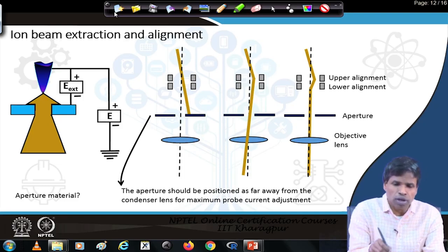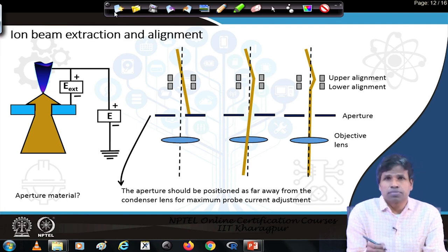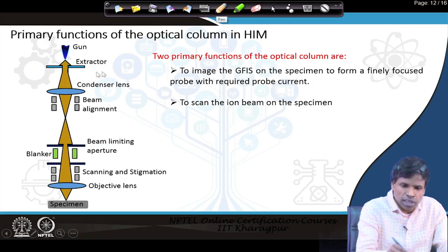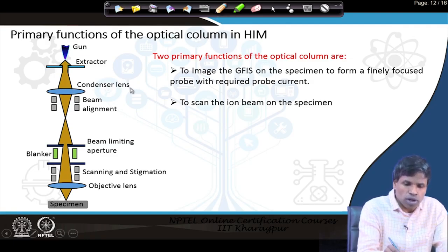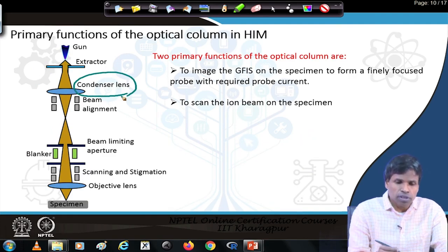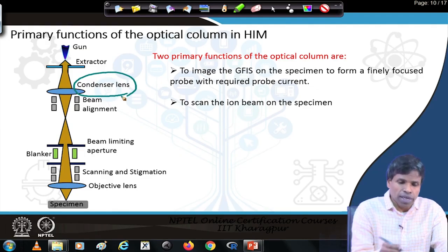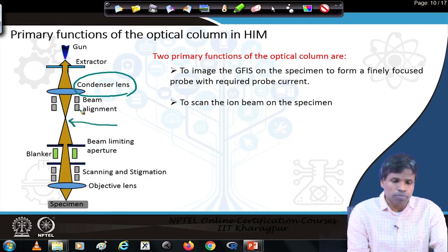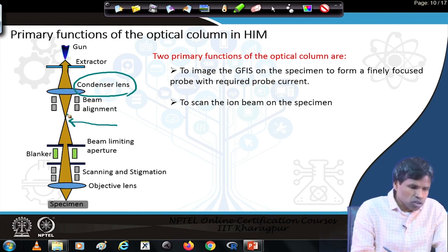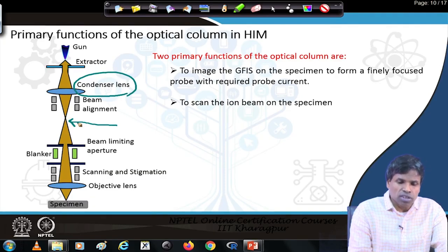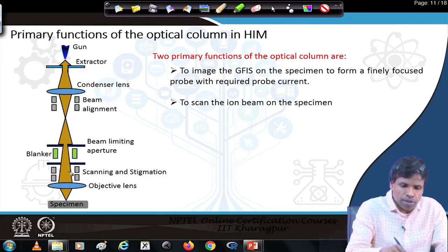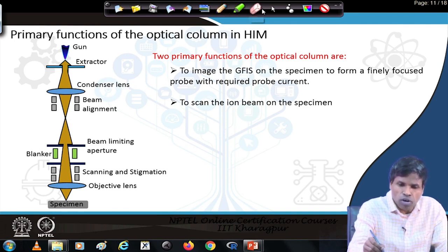Once the beamlet comes downwards, it first encounters a condenser lens. The condenser lens condenses the beam — in this case the ion beam — and forms the first crossover inside the column. The beam falls on the condenser lens and forms the first crossover. Below the condenser lens we have the beam alignment process, and this beam alignment ensures the beam falls directly on the optical axis so that it aligns along the objective lens.